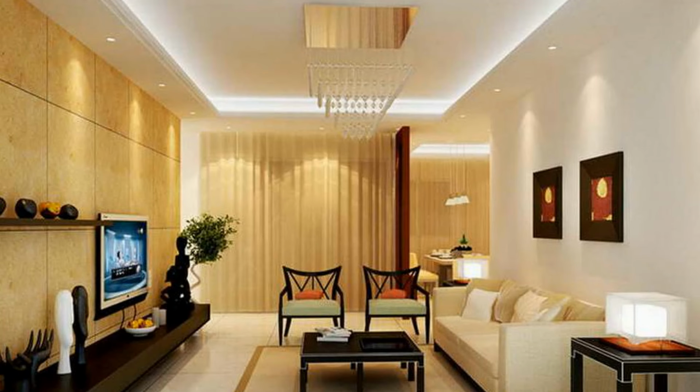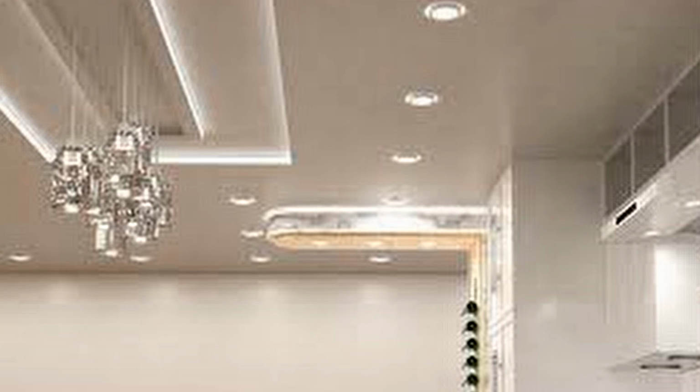First costly mistake, burying the drivers in the ceilings. Drivers generate heat. Yes, it's always going to be in the ceiling void between the POP and the concrete slab, but you need to make sure there's enough height so that there'll be enough natural air movement for those drivers. But I've seen people burying the drivers in the concrete, which is madness. I think that was an amateur contractor, to be honest. That is going to overheat, and that's going to be a disaster waiting to happen.